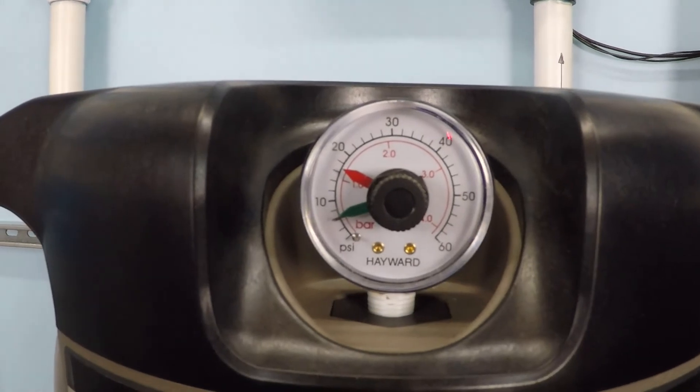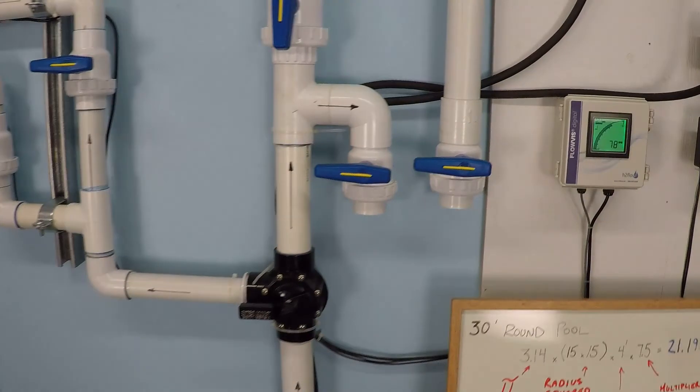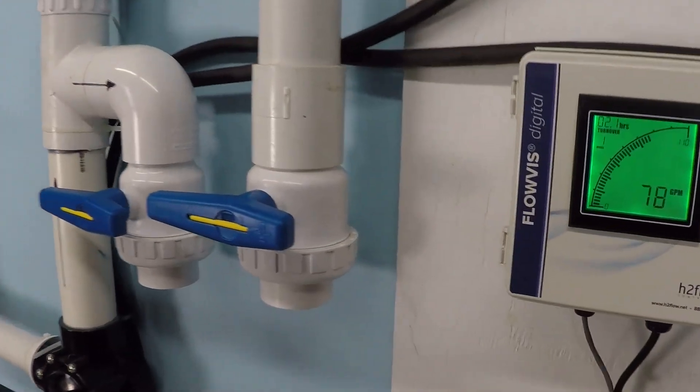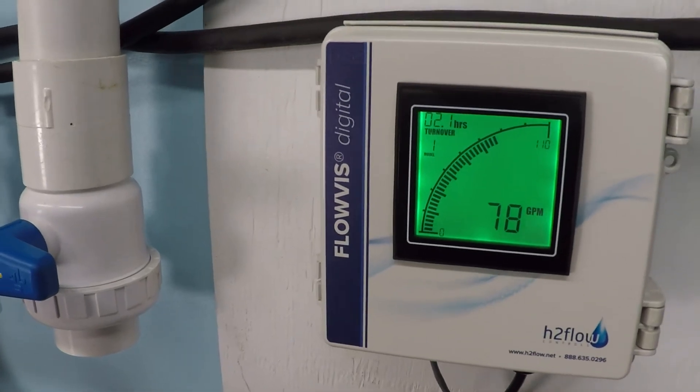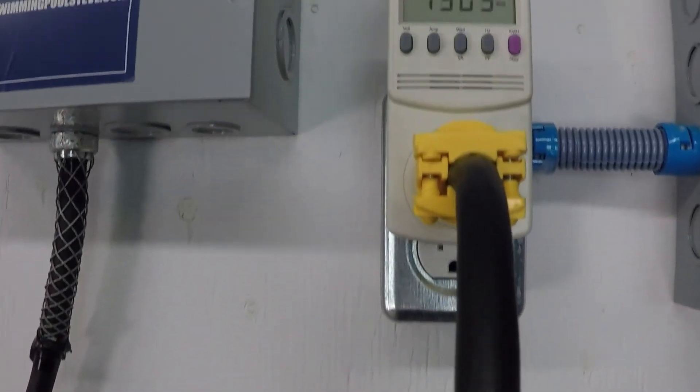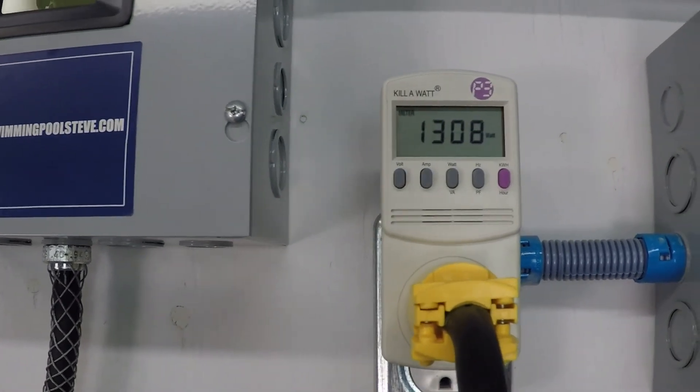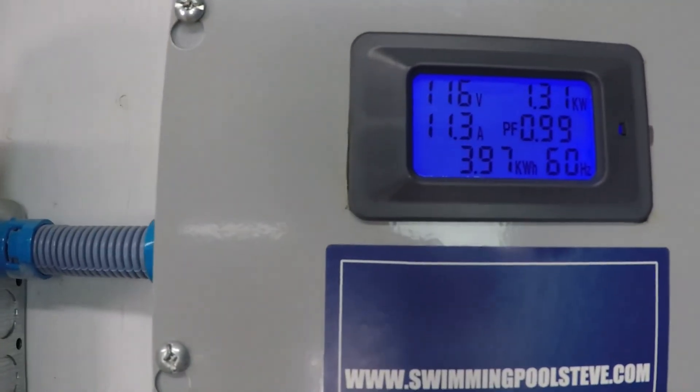Let's take a look at our filter pressure here. I'm going to call it about six PSI. 78 gallons per minute. That's quite a bit. But it's costing us a lot of power consumption here. Over 1300 watts, 1.3 kilowatts.